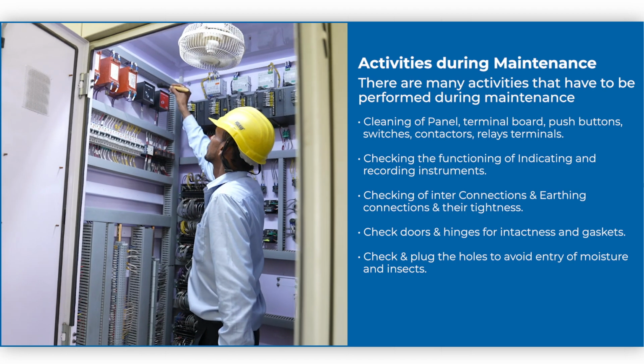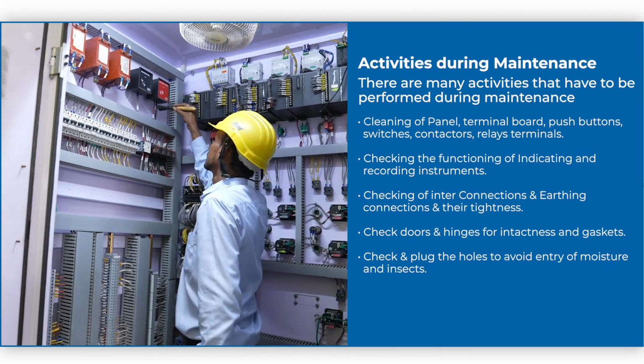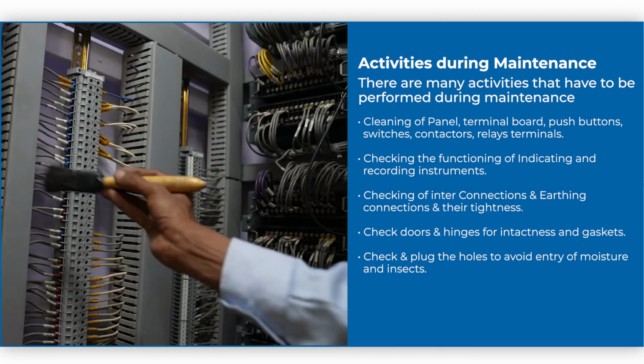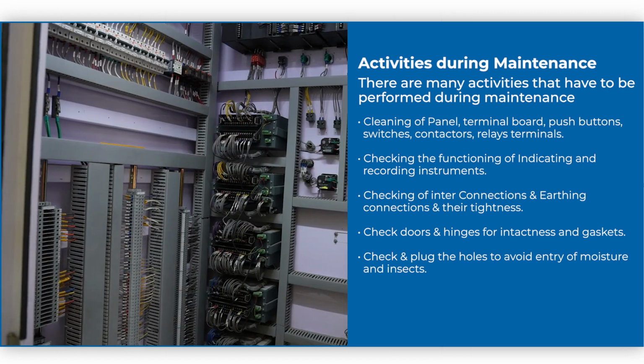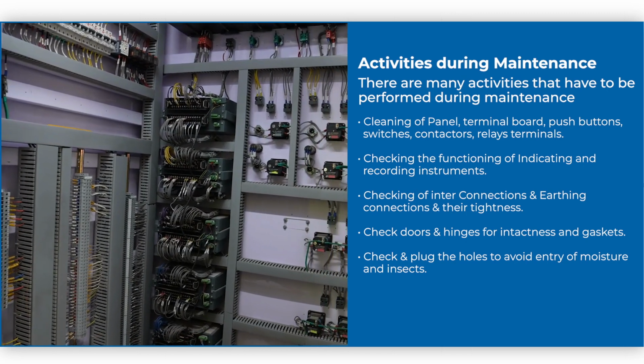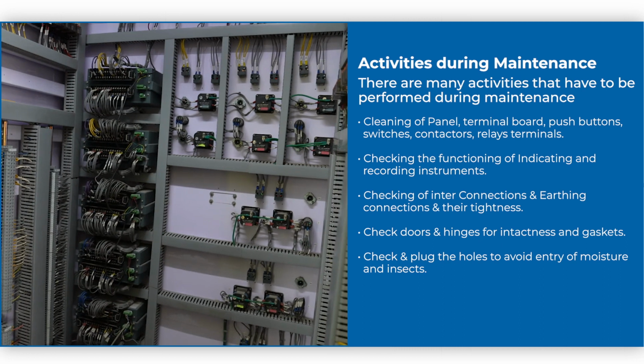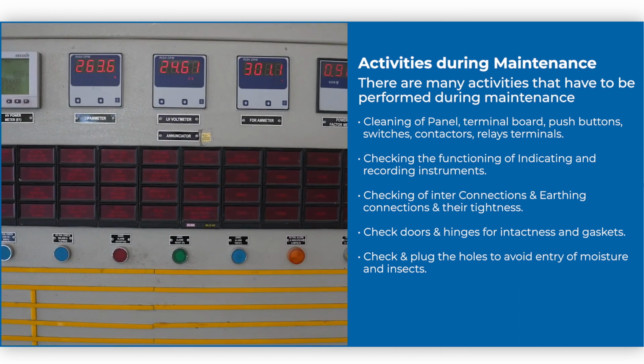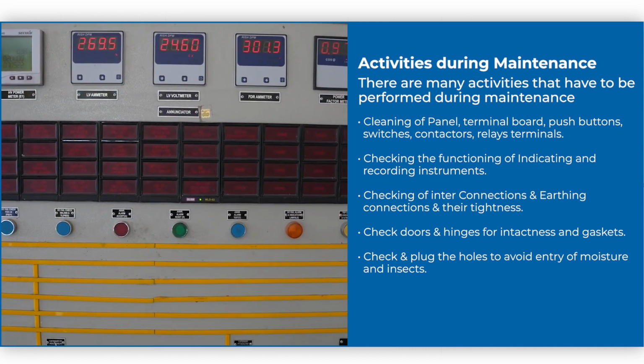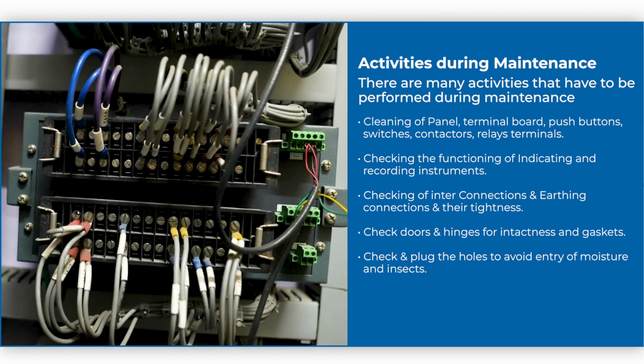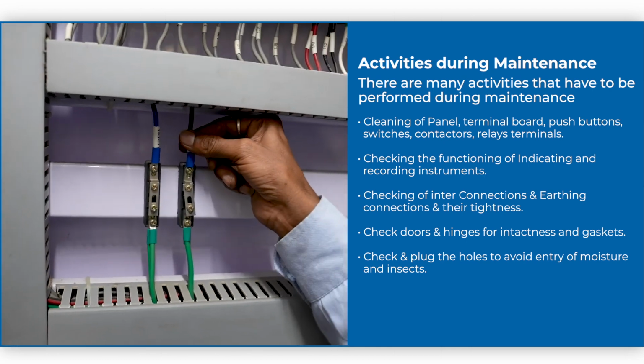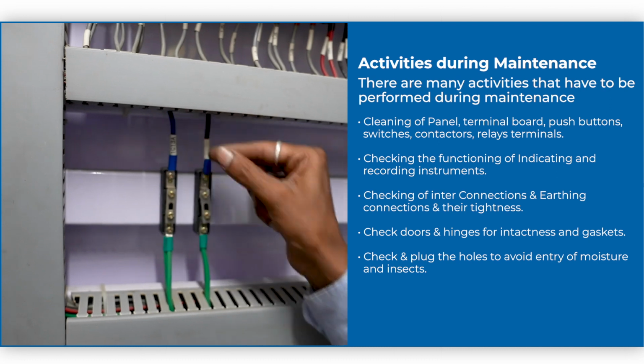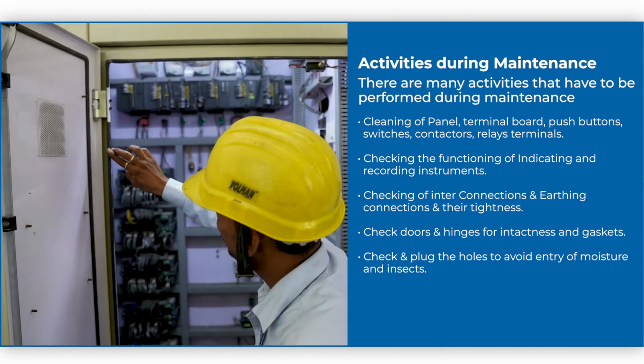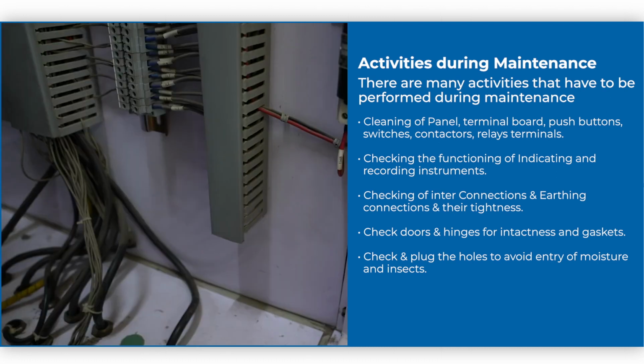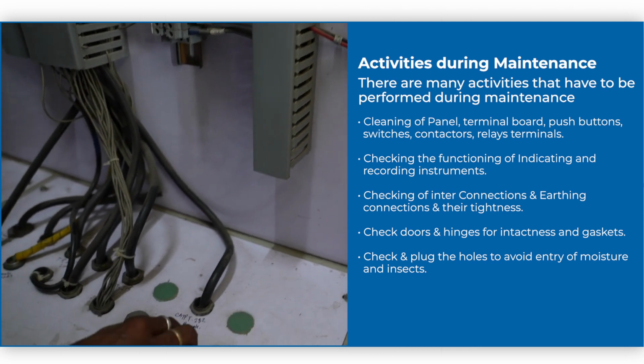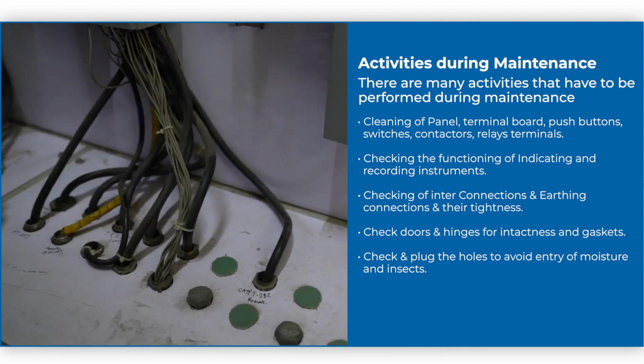There are many activities that have to be performed during maintenance. Cleaning of panel, terminal board, push buttons, switches, contactors and relay terminals. Checking the functioning of indicating and recording instruments. Checking of interconnections and earthing connections and their tightness. Check doors and hinges for intactness and gaskets. Check and plug the holes to avoid entry of moisture and insects.